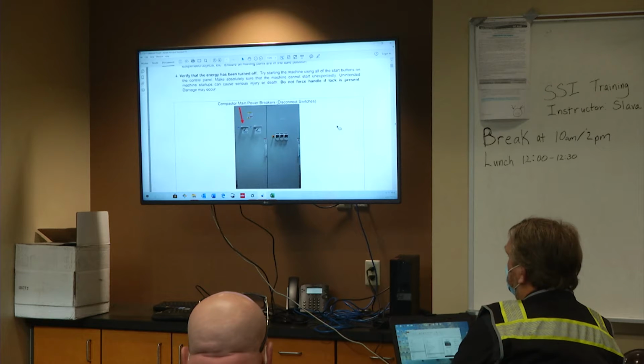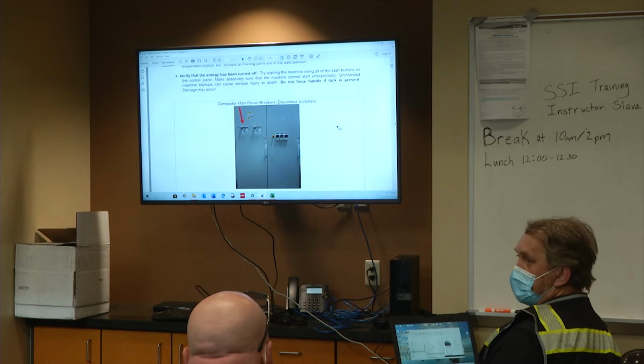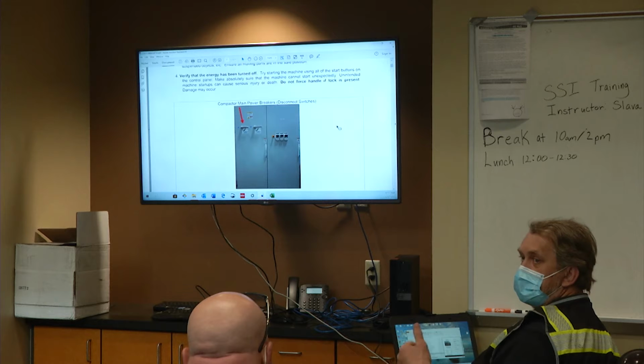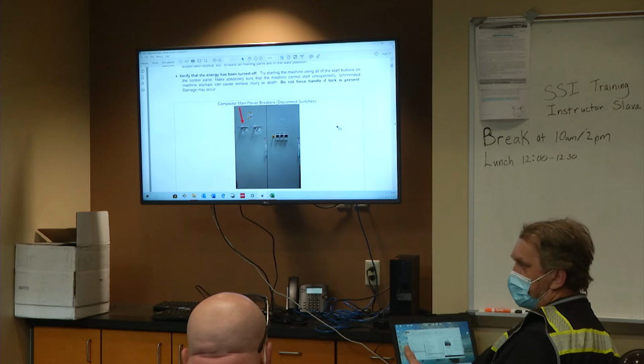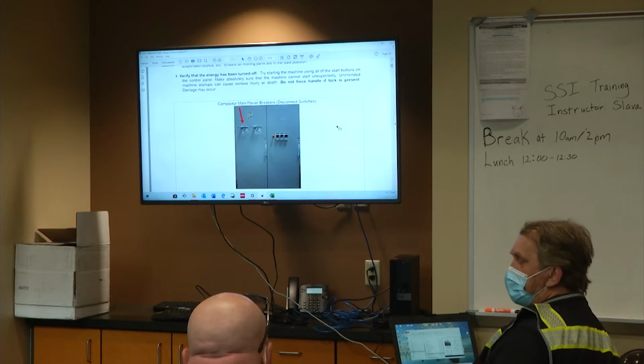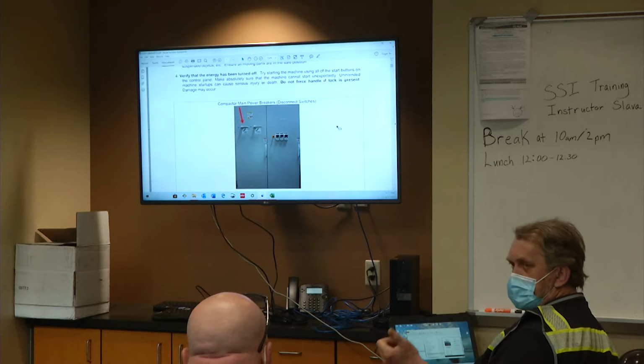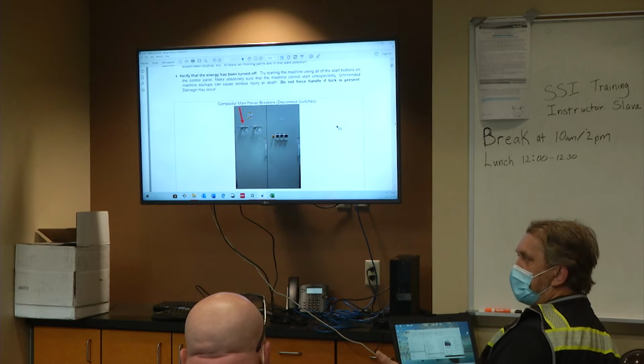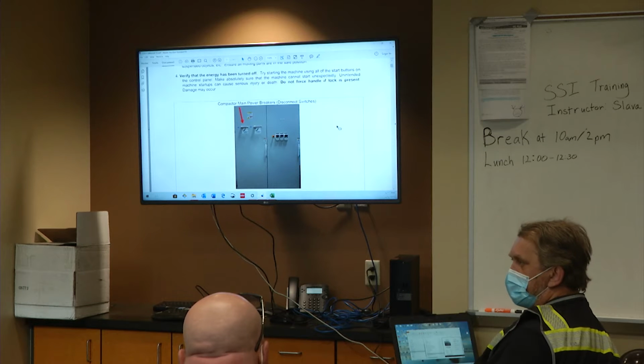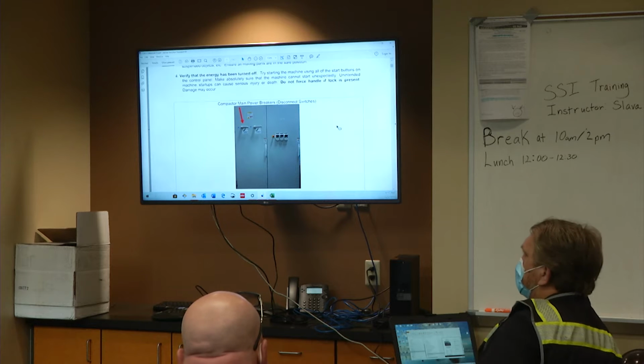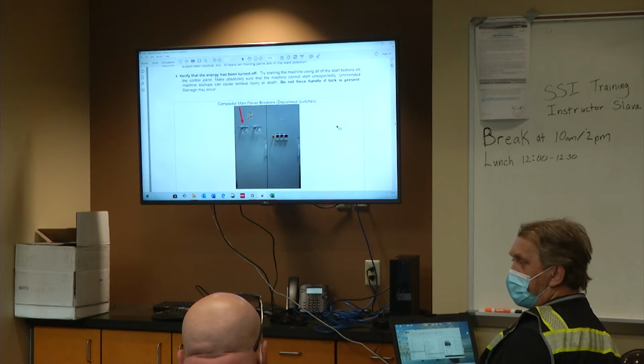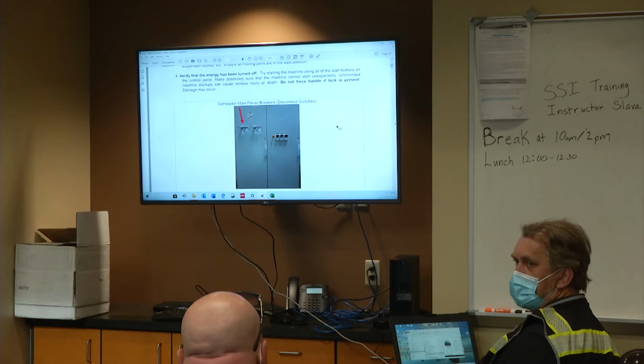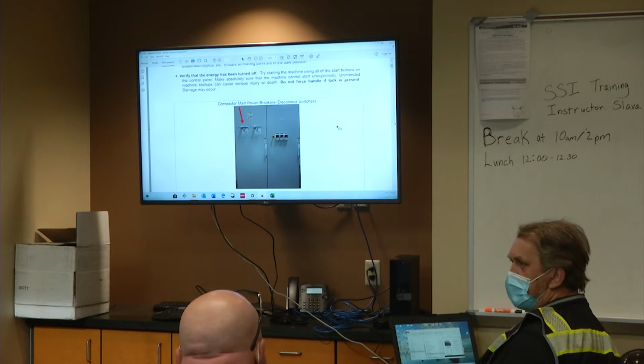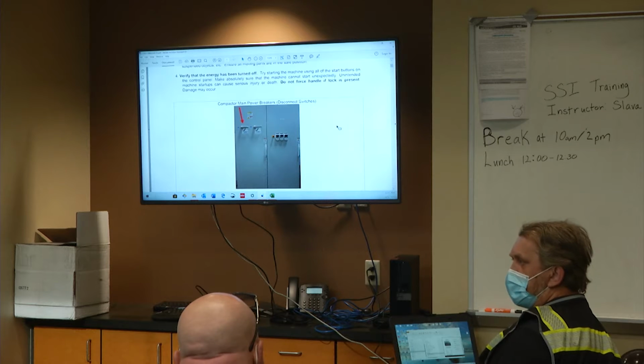There's also, you want to verify that there's no mechanical pressure, and although the system is designed to relieve pressure automatically, so as long as you have HPU off, main key switch off, and obviously locked out, tagged out, at that point, usually as soon as you turn off the main key switch, your pressure is released automatically. We do encourage to do a manual release also, but that would be at your manager's discretion. But the system is designed to automatically dump pressure.